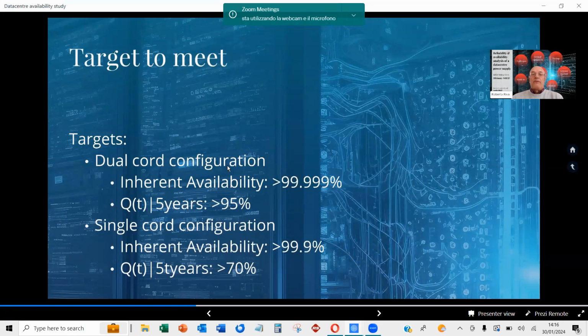For single cord configuration, a kind of degraded configuration of the system, in our case configured as two systems, one in each data hall being out of use, we had an inherent availability greater than 99.9%, and a probability of failure at 5 years greater than 70%.